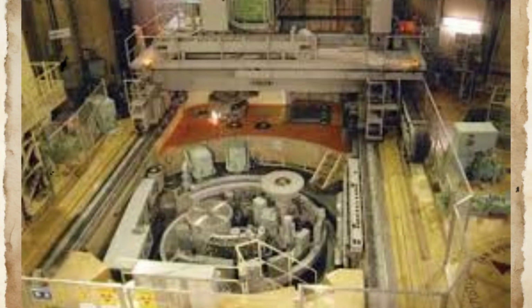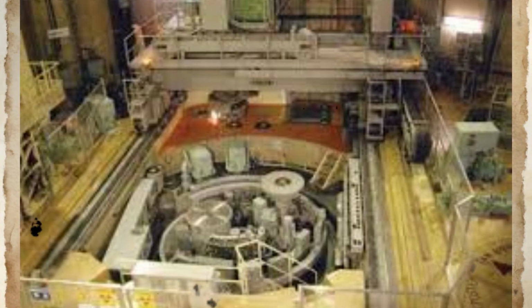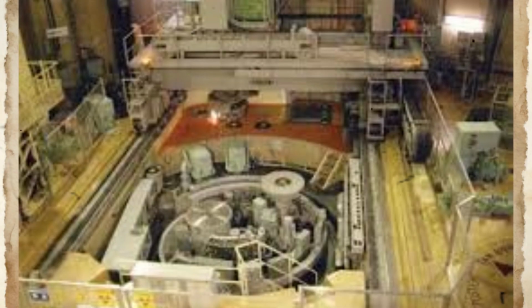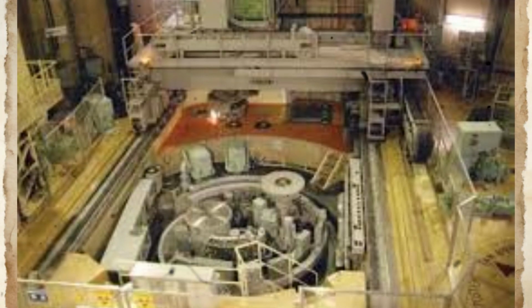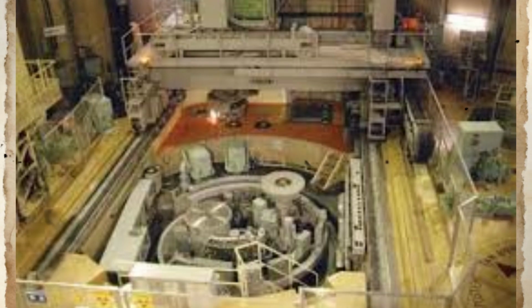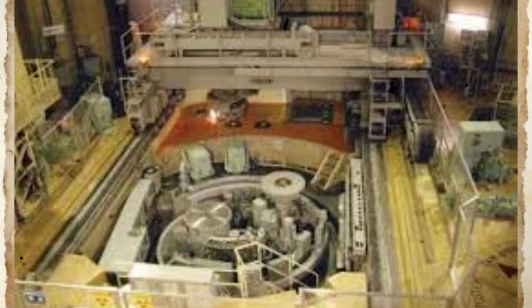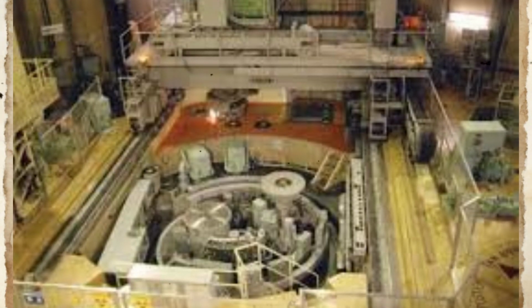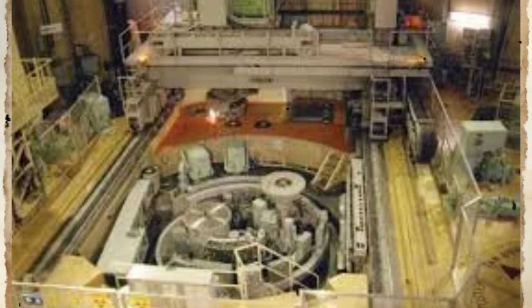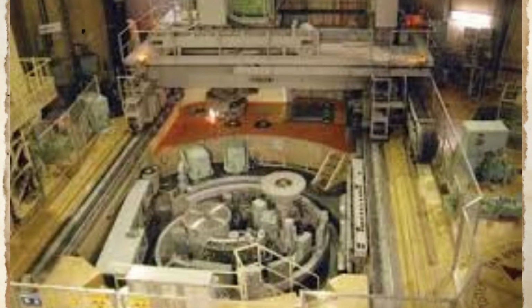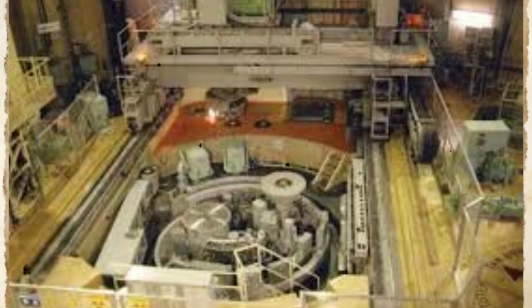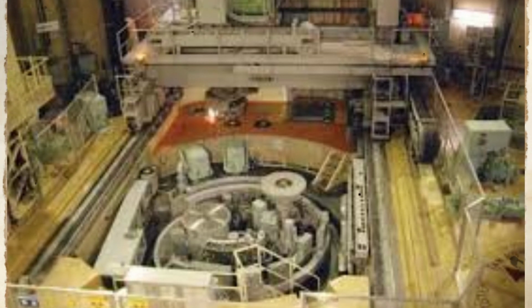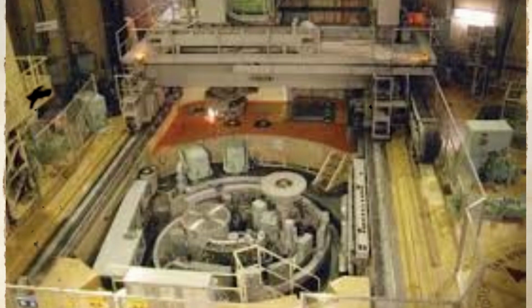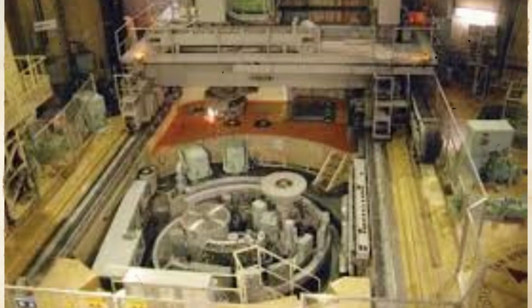The location of the failure also contributed to diagnostic complexity. The thermocouple well was positioned near the outlet of the intermediate heat exchanger in a region of the secondary heat transport system where high temperatures and flow rates created challenging operating conditions for instrumentation components. However, identical wells in the same locations in loops A and B continued operating normally, suggesting that the failure was not simply a result of excessive operating conditions.